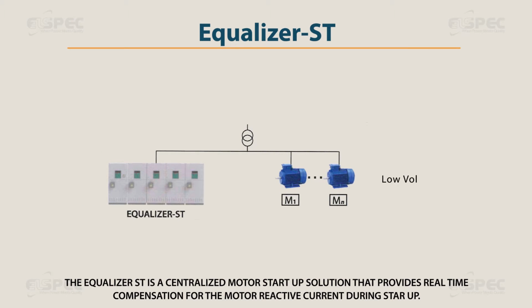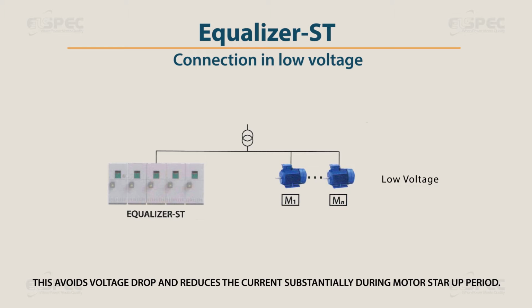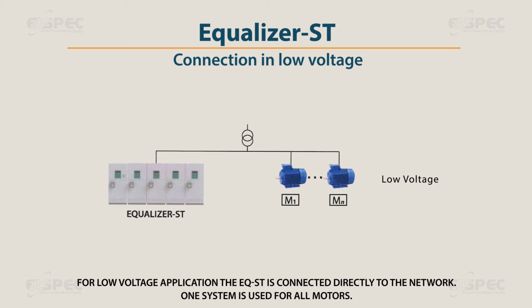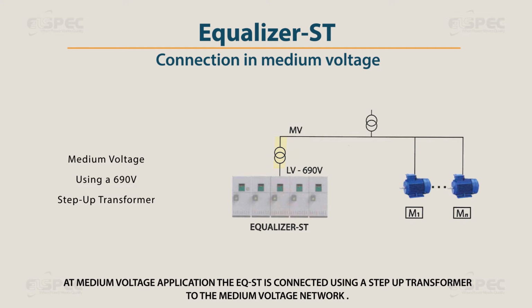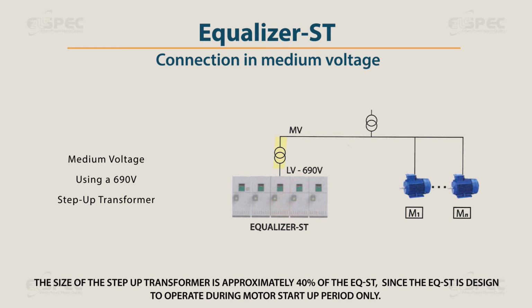The Equalizer ST is a centralized motor startup solution that provides real-time compensation for the motor reactive current during startup. This avoids voltage drop and reduces the current substantially during the motor startup period. For low-voltage applications, the EQST is connected directly to the network. One system is used for all motors. In medium voltage applications, the EQST is connected using a step-up transformer to the medium voltage network. The size of the step-up transformer is approximately 40% of the EQST, since the EQST is designed to operate during the motor startup period only.